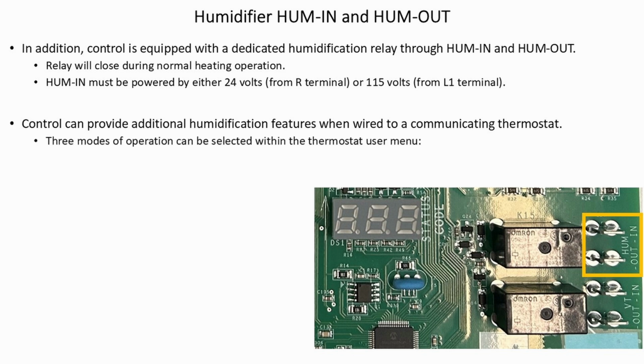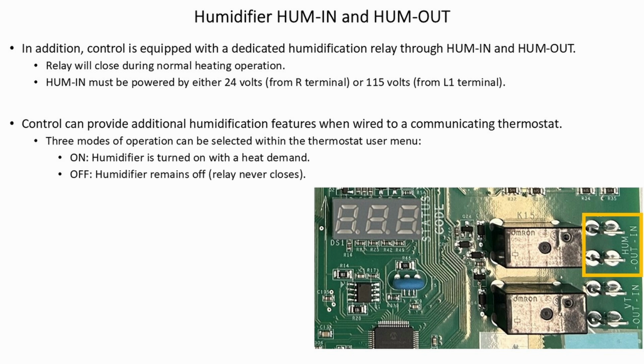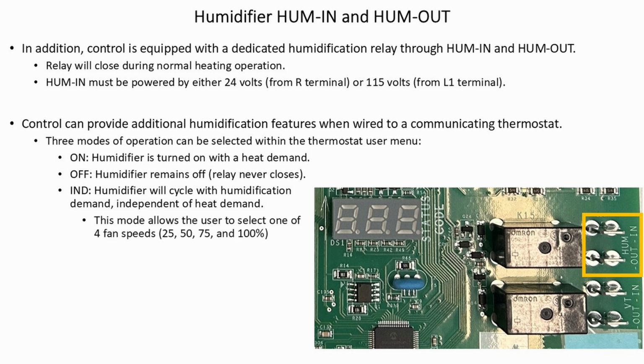Three modes of operation can be selected within the thermostat user menu. On: humidifier is turned on with a heat demand. Off: humidifier remains off, the relay never closes. IND, or independent: the humidifier will cycle with humidification demand independent of the heat demand. The mode allows the user to select one of 4 fan speeds: 25, 50, 75, and 100%.